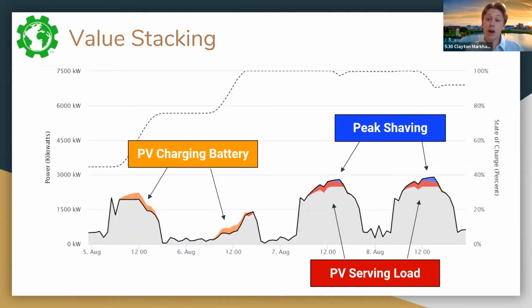This is a graphic showing our value stacking strategy. Since Ball State is charged based on the peak 15-minute integrated consumption interval for each month, a peak shaving strategy is best. In blue, the battery discharges; in red, the PV serves the load, mainly between 10 a.m. and 5 p.m., to offset that peak demand. In orange, the PV charges the battery on days when total consumption is lower, also represented by the dashed line showing the battery's state of charge.